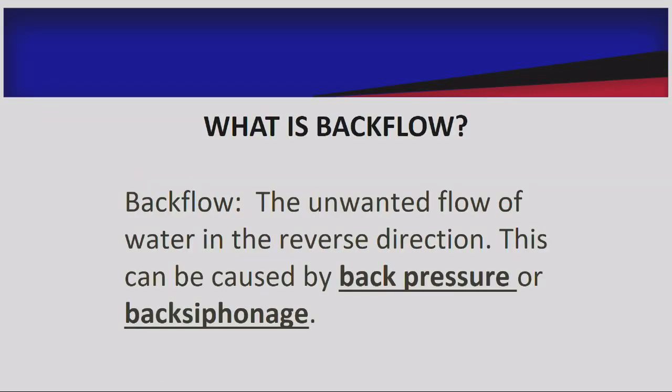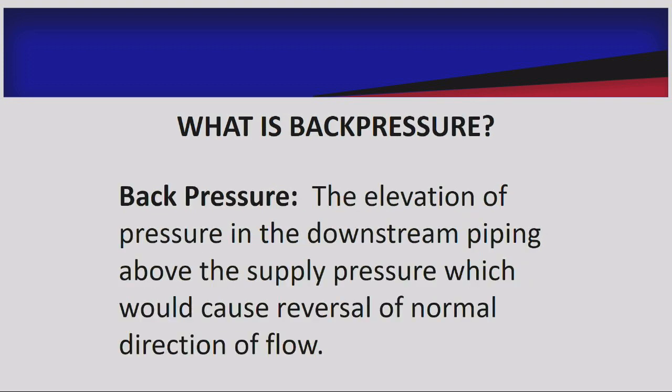So what is backflow, right? Backflow is the unwanted flow of water in the reverse direction. And it comes in two forms, either back pressure or back siphonage. Back pressure is literally when the pressure in the building is higher than the line pressure and water flows into the line, out of the business's plumbing, into the distribution system. And so you get the backwash of some business.